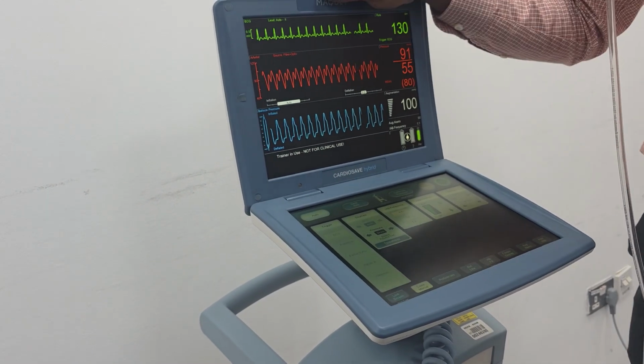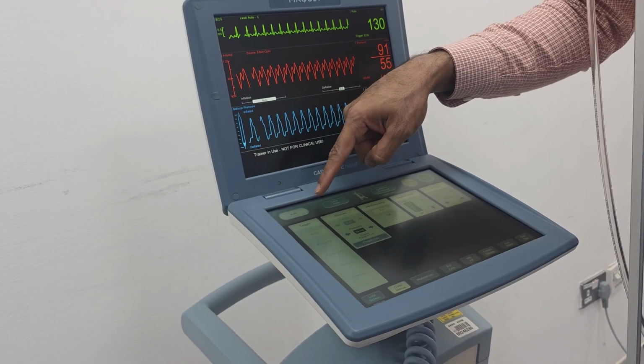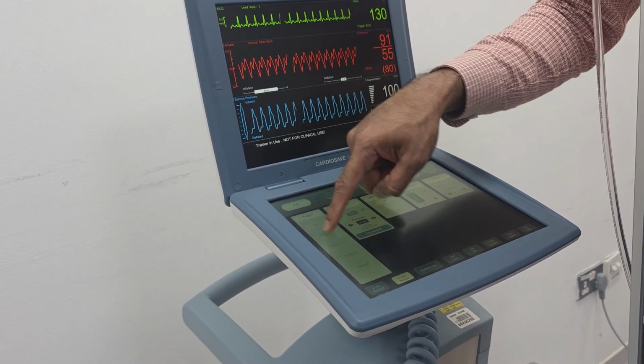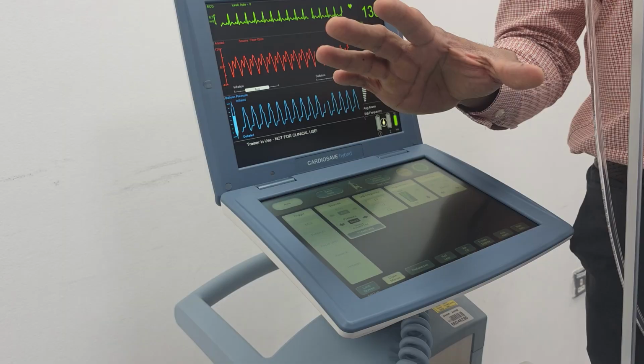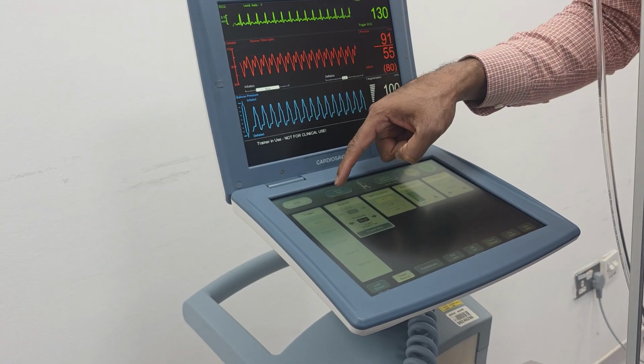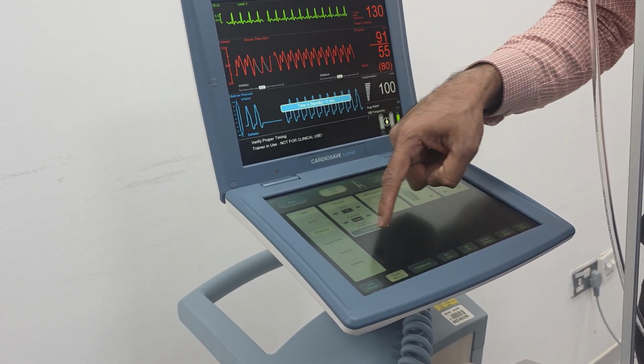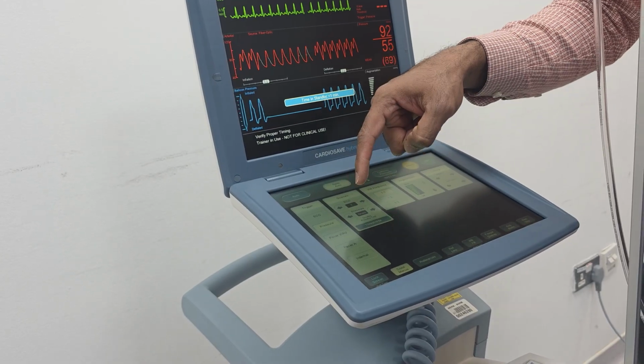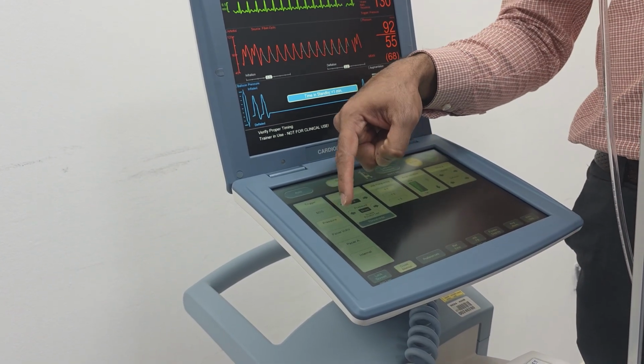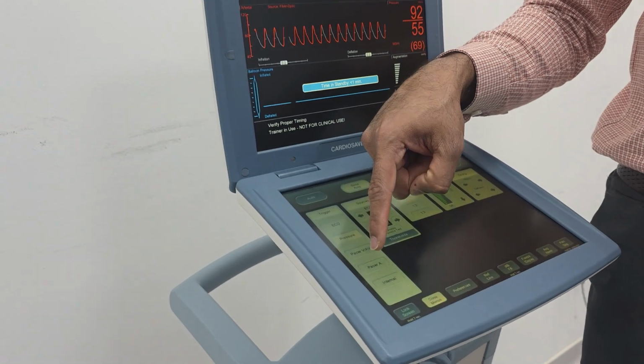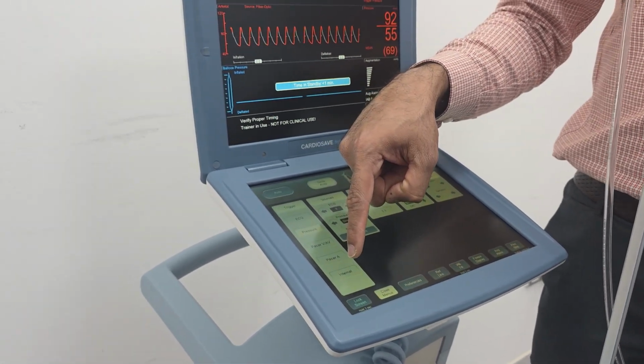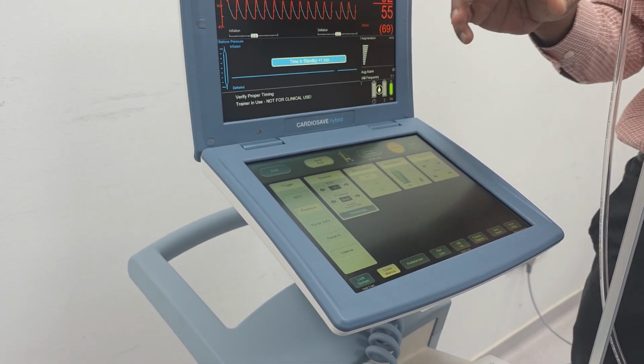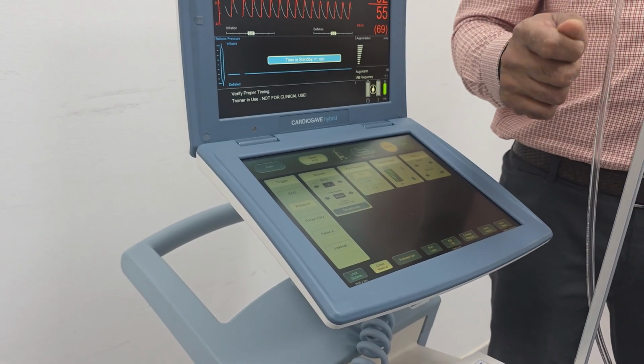Again, same like CS300, it's an auto mode. You don't have any control on this trigger mode. You will choose automatically. Okay, we are in auto mode. But when you are in semi-auto mode, if you want to choose pressure, you can choose a pacer 2 modes. If the lead is in ventricle or atrium and ventricle, you can choose this. Or if the lead is only in atrium, you can choose this. Internal mode, they will only use mostly during the transplant time.